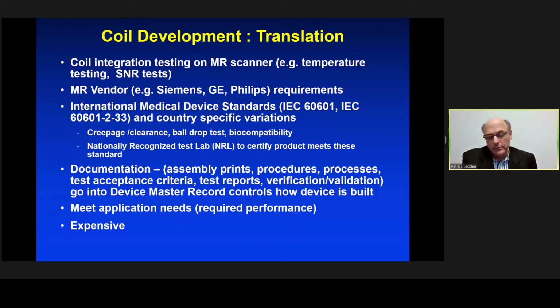Once you have your coil, you're going to need to do some verification, and particularly you're going to have to do some coil integration testing on the scanner. Does it work? And particularly you need to look at the safety, such as temperature testing, maybe the performance as well, SNR tests. All MR vendors have their own requirements, and to sell the coil on their scanners, you typically need to show them that you meet these requirements.